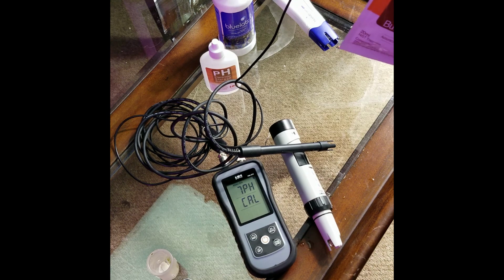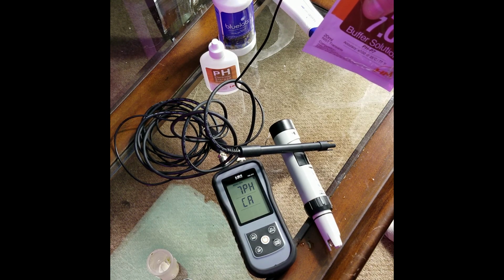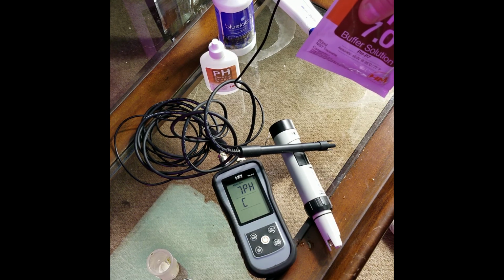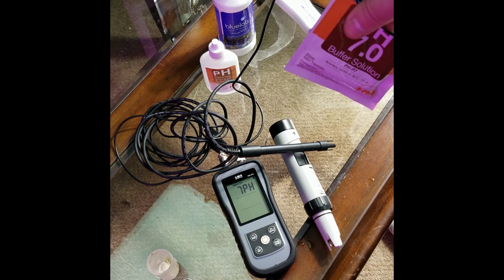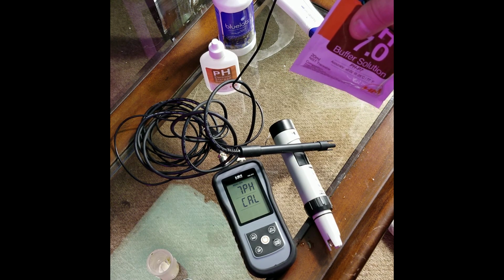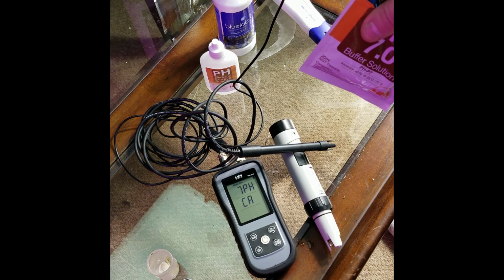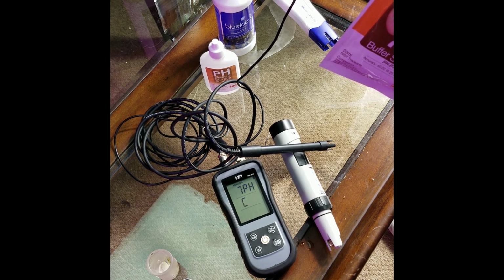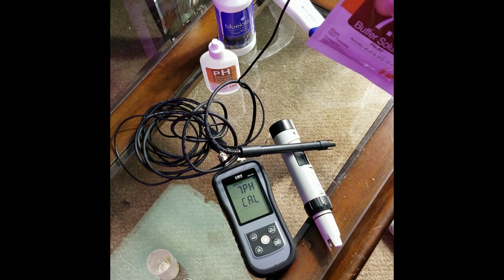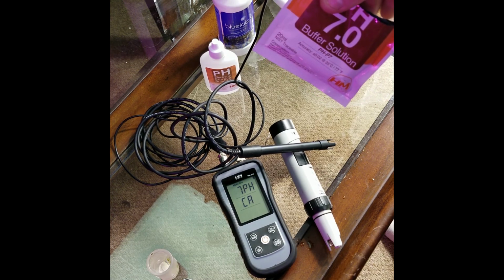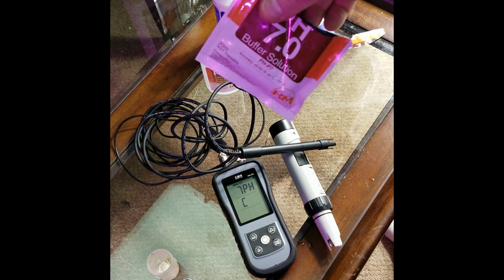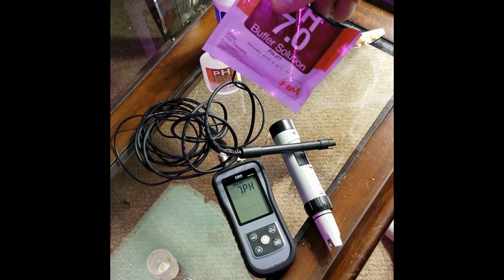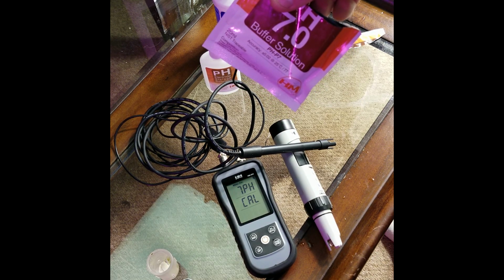Okay, so this one, what it's doing is it's sitting there, and it's just reading it to make sure it doesn't jump up by 0.1 or down by 0.1. And so after, I think, another 10 seconds here, it'll flash calibration, it'll say end, and it'll say 7. So it automatically knows that you're doing 7 because you chose 7, and so it sets 7. I'll show you how it's different on the other.